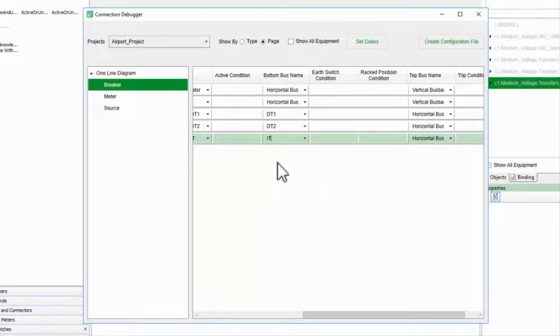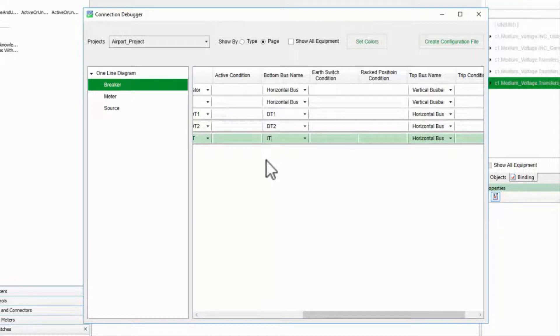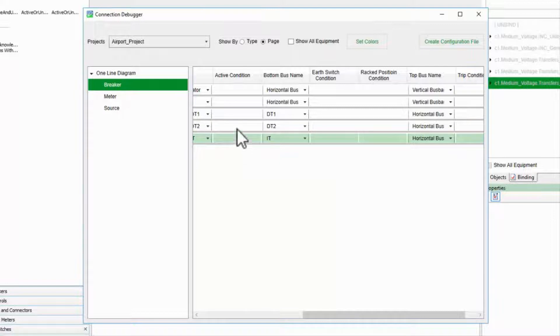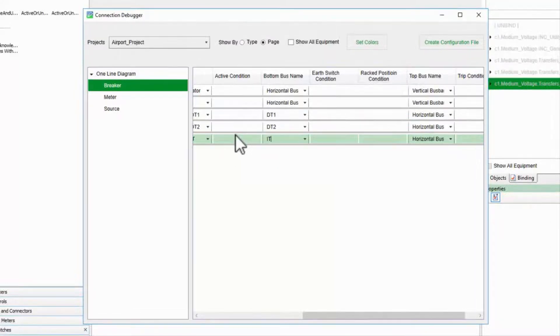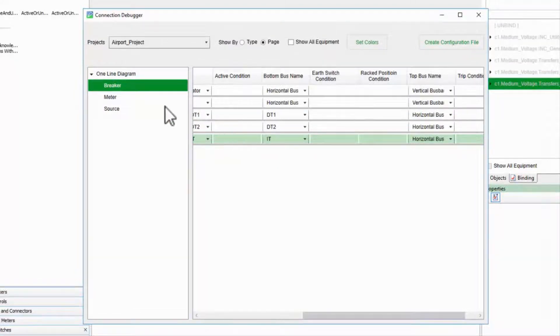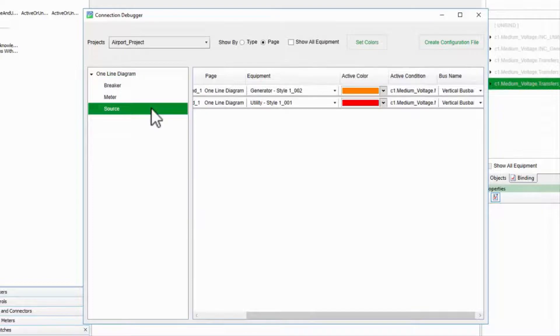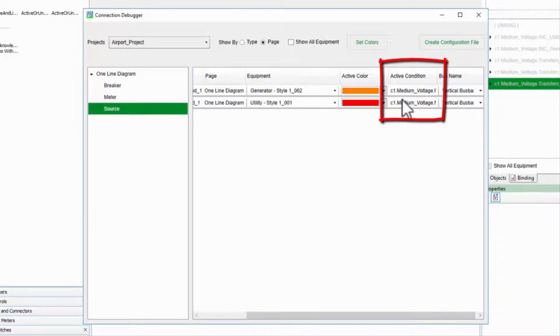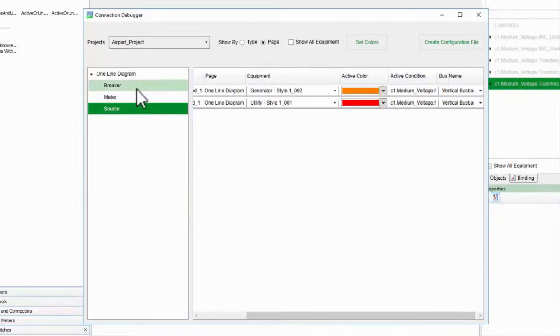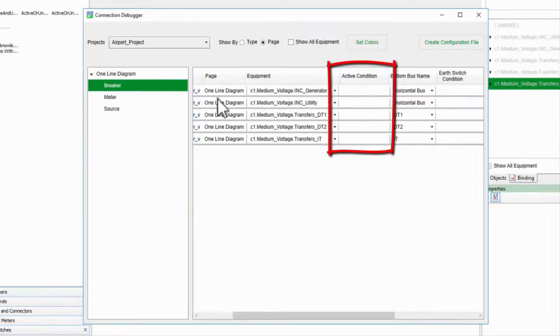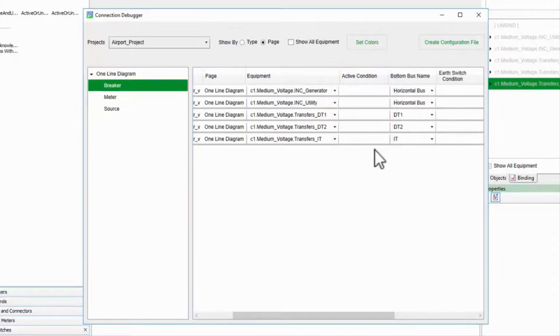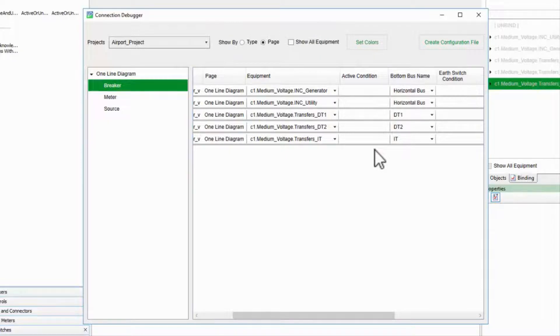While I'm here, observe that I can set the parameters for any of my one-line components in the debugger. In fact, you may find that it's easier to configure the sources active condition, or custom breaker states, here, rather than in the graphics themselves. Whatever changes I make here are automatically written back into the page.